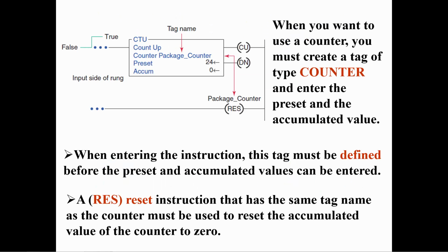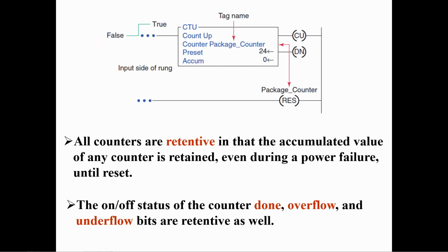You must define the counter by creating a tag before entering the preset value. A RES, or reset instruction, is typically used to reset the counter's accumulated value to 0. Counters are retentive in that the accumulated values and the status bits are retained even during a power interruption.